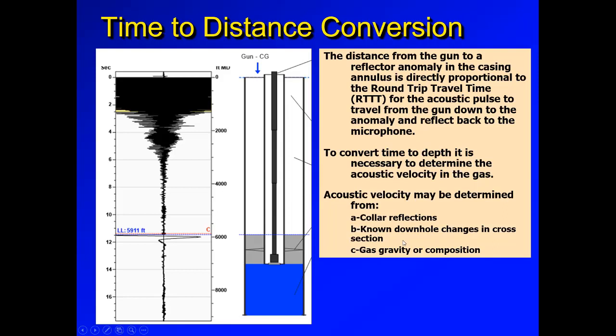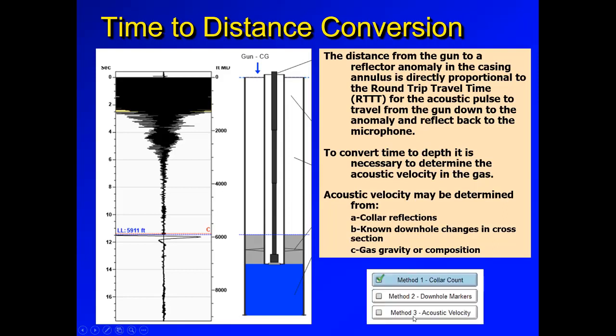How do we cover this in the software? We give you three options. Method one uses a collar count. Using a change in diameter, we call that a downhole marker - if you have any kick in the well at a known depth, you can use that as a reference point to calculate velocity, and with velocity and time, calculate distance to liquid. The third option we call acoustic velocity, which includes using gas composition, gas gravity, or manually inputting the acoustic velocity. We'll talk about these three methods next.